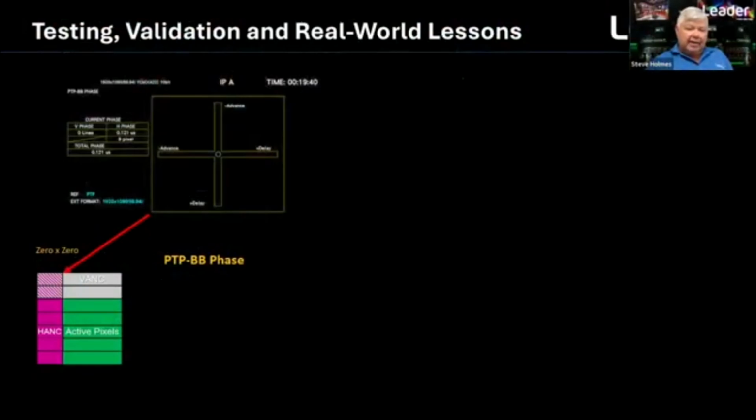There's no need for it. So the starting point of black is line 0, pixel 0, right here at the top, up here, my 0 by 0. Well, PTP should be at the same exact point that black burst is. So when you look at your IP input and you look at timing, and you're referenced against black, it should come up with 0 by 0.